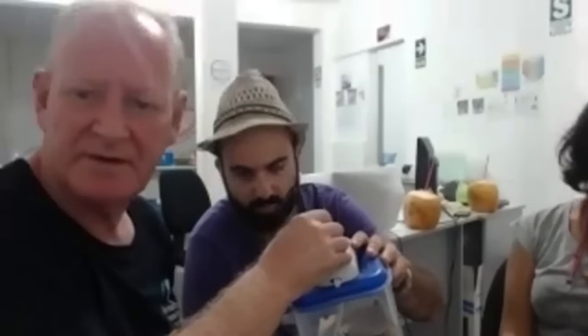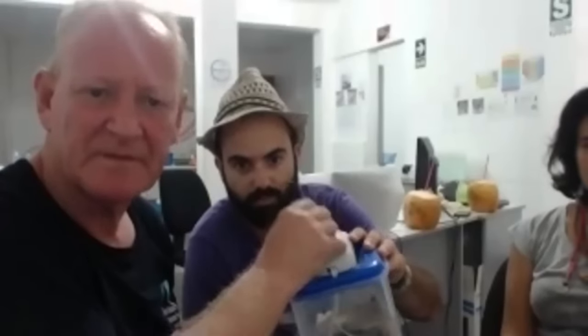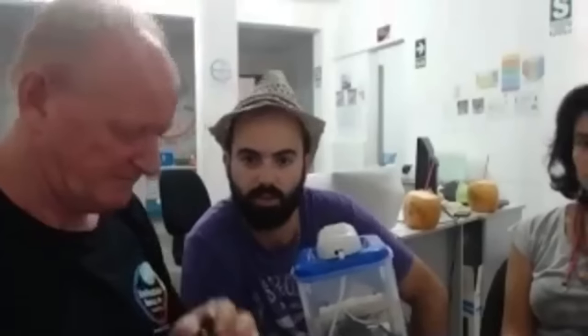We're getting nothing. Perfect. Okay, that's good. It should be infinite. You can get away with 500K, 500,000 ohms resistance or higher, but ultimately it should be infinite.